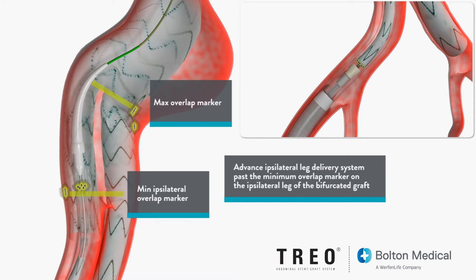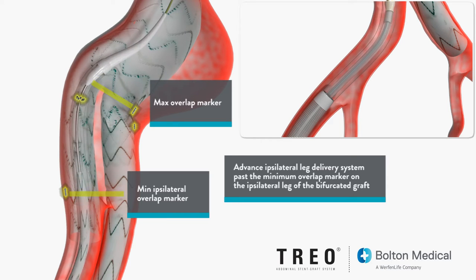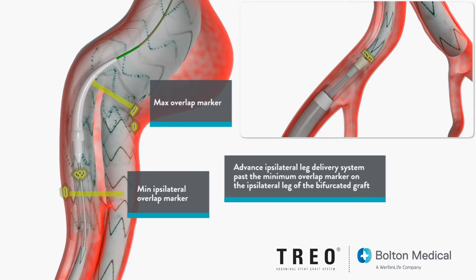The ipsilateral leg of the main body has a single marker that indicates the minimum overlap. The maximum overlap marker is the same marker as used on the contralateral side. The proximal end of the leg extension must be advanced so that it is between these two markers, while ensuring that the distal leg marker position is at the desired location.